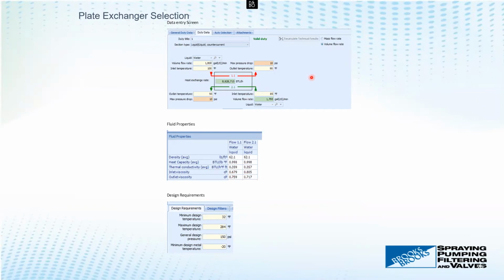Now this is a real world selection we've had from a customer fairly recently. It's 1800 gallons per minute of warm water, only 100 degrees hot coming in. They're using cooling water at 85 degrees coming in, and heating that 85-degree water up by 10 degrees, with 10 PSI pressure drop allowed on both sides.